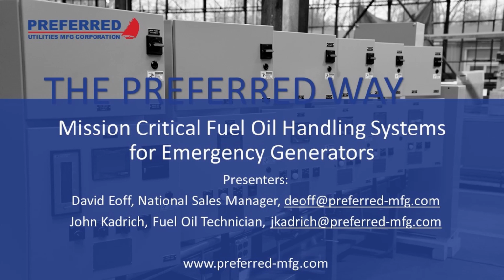So, John, whenever we do a transfer pump set, we ship a paddle type switch loose. Correct. For the contractor to install. Are there any do's and don'ts about where to put that flow switch? You always want to put it on a horizontal run. I have seen people try and do it vertically, and it's not accurate. The paddle will open and close without the fuel going through the way you want. If you plan on doing under 3 gallons a minute, you have to go with the electronic high-tech flow switches, because our paddle switches don't go below, I think it's 5 gallons a minute.